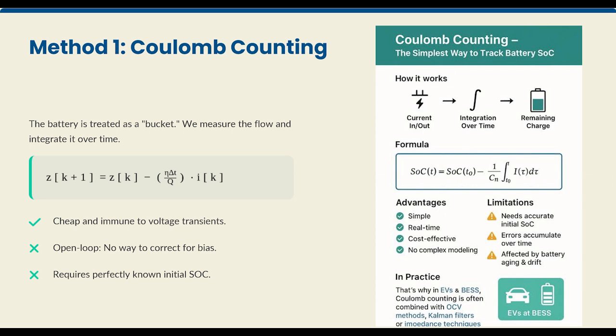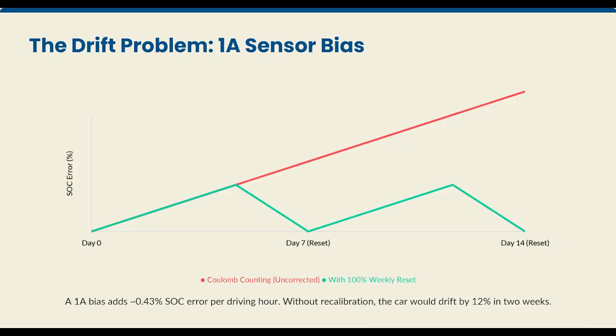As you can see on the formula side, it's an open loop system to measure and estimate, so there's no way to correct for a bias. The drift problem is really important because a little bit of bias, like 1 amp adding up every hour, can lead to a drift of 12%.